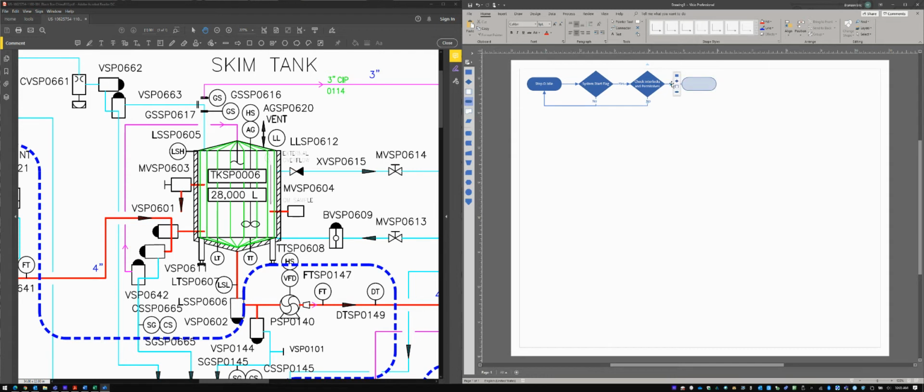If we pass our interlocks and permissives, we're going to start up and go to the next step. Each step is specific to the outputs that it has. The inputs of the system allow it to change steps, and then each step has its own set of outputs.